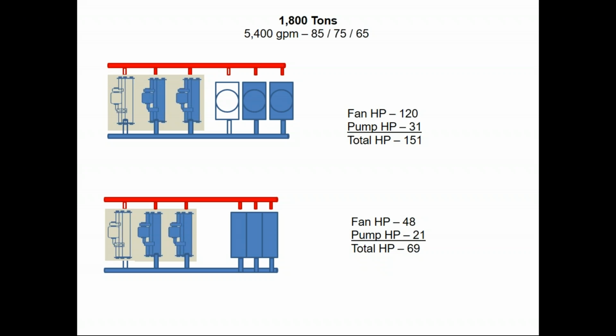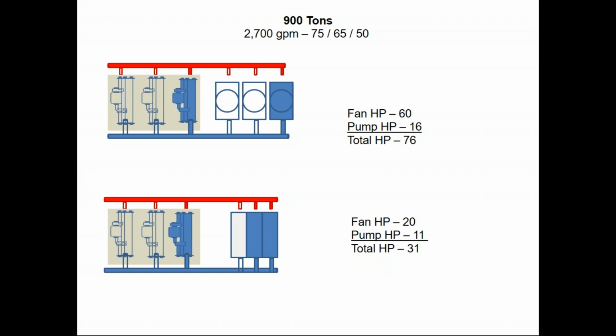In the TowerTech solution, because we can operate with variable flow through the tower system, we're going to operate 2 chiller flow through 3 tower cell. So we're going to have a ton of surface area on the fill side of it, and then we're able to reduce the horsepower of the fan system, and we also are operating with less pump head. So we have a total horsepower savings of 82. We have a total horsepower of 69. So we have a 54% advantage on a multiple chiller plant in this case. I had 1,800 tons in this one.